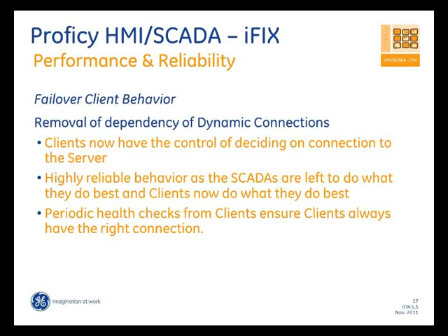We saw that the clients accurately follow the active SCADA. When it goes into maintenance mode, it follows the standby SCADA, which becomes active once you get to maintenance mode. But we have seen a highly reliable behavior of clients now moving across that.